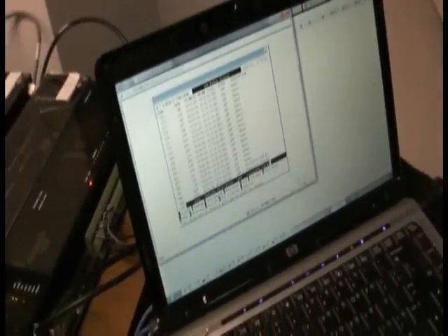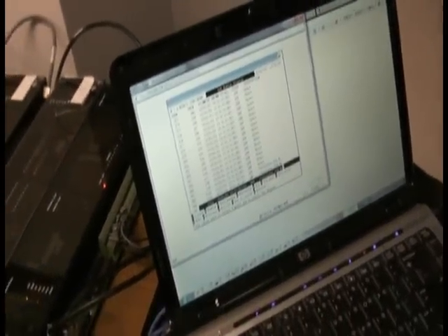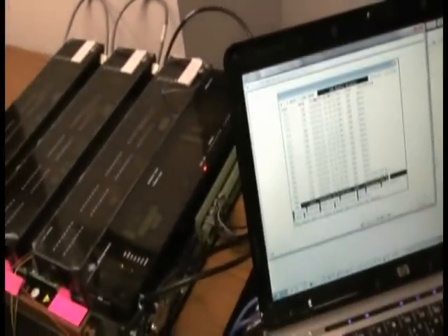If we go back to the SOE log, take another look, we'll see if we just run right to the end, we've got all 384 points on and off, and we have three calculator points that are triggered off of one status point on each board, which is what the extra points are. So as you can see, it's very, very responsive, very quick updates for status inputs coming in from the D.20 link.